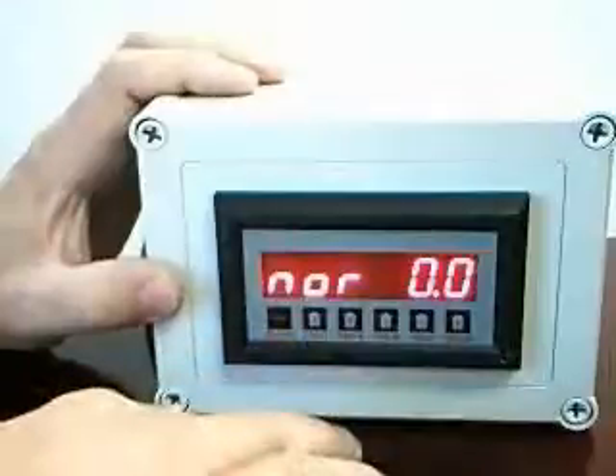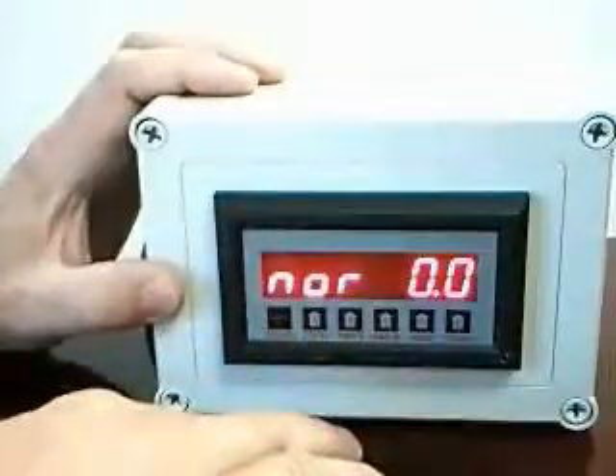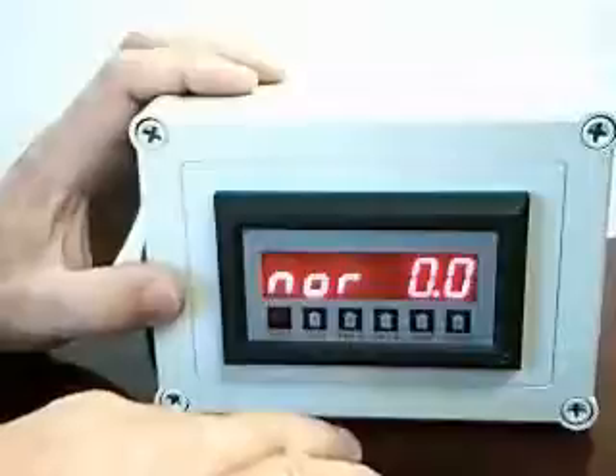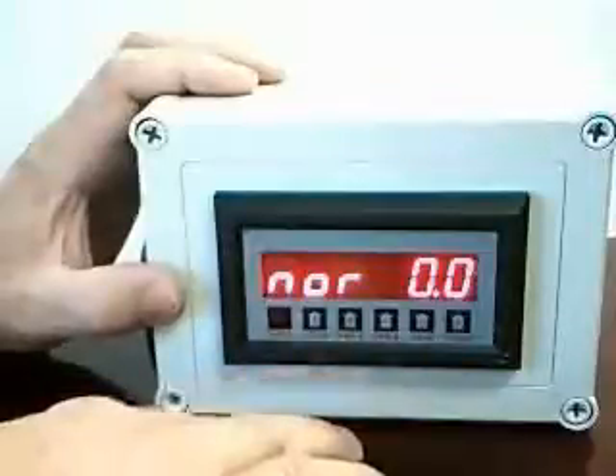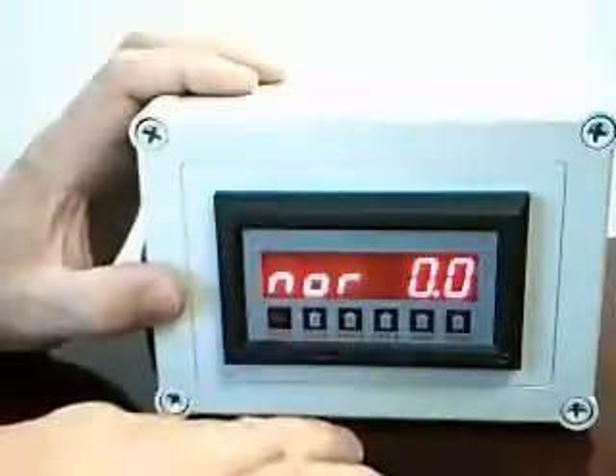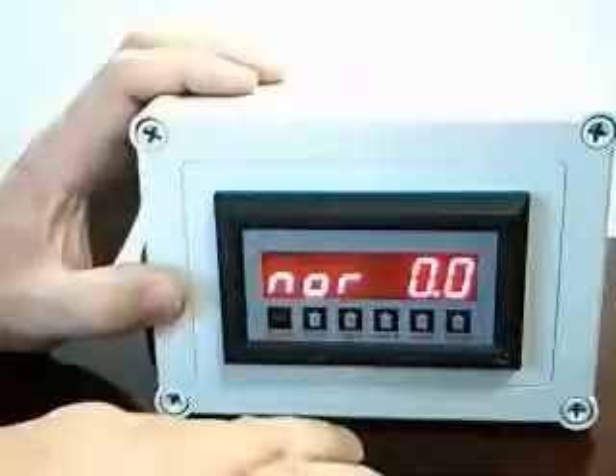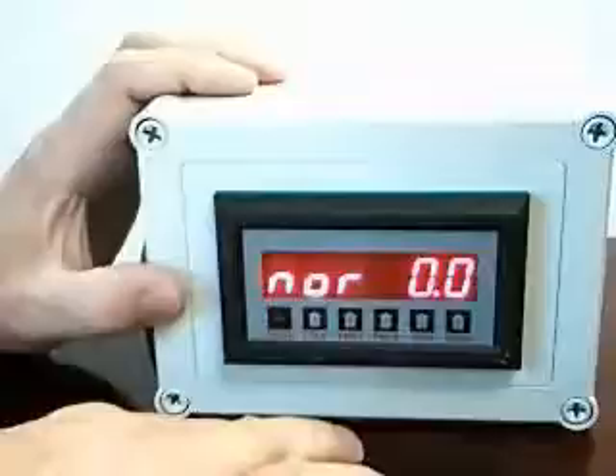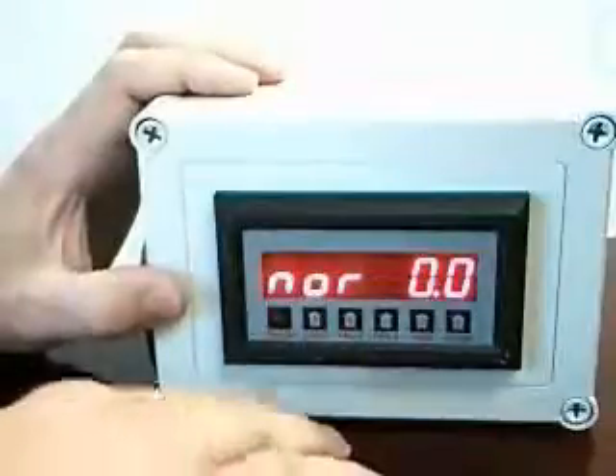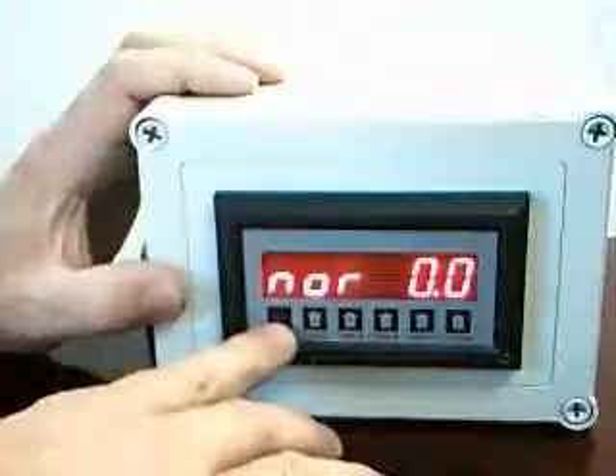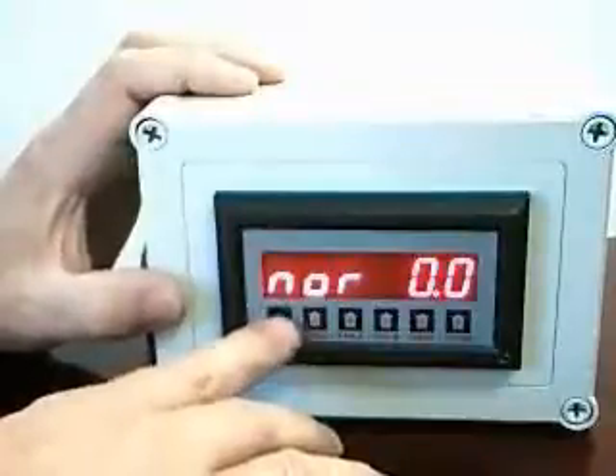This next menu, normalization, is an averaging constant. This may be used once the system is online if pulsations and flow are observed that are objectionable to the rate display. Increasing the number entered here provides additional averaging. We're going to start out with no averaging in this instrument.